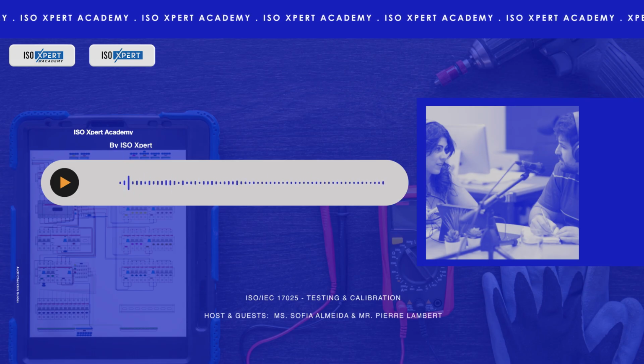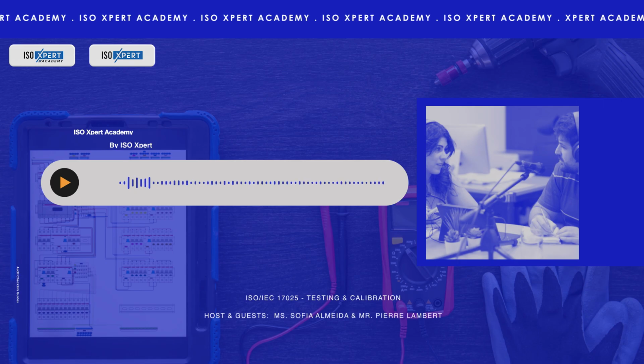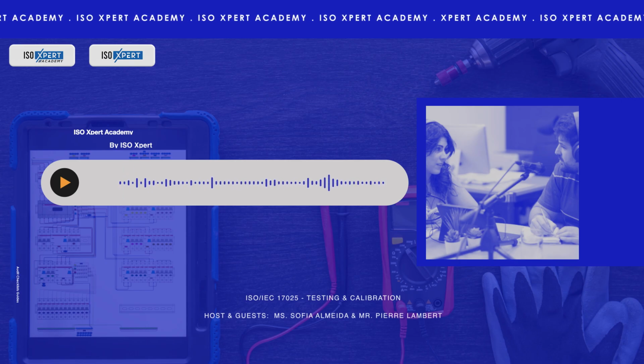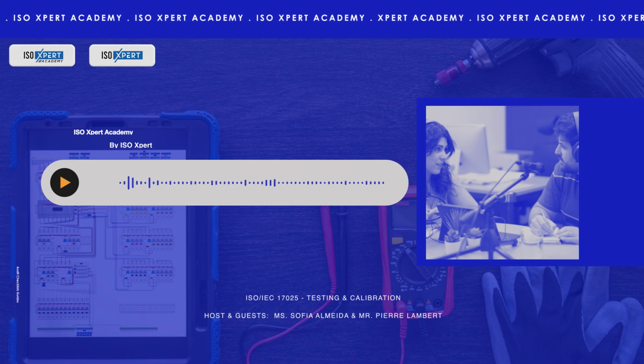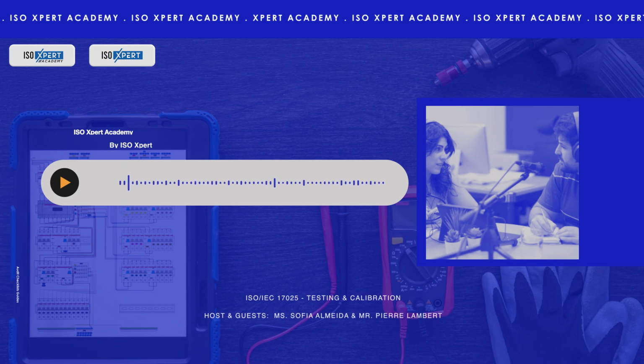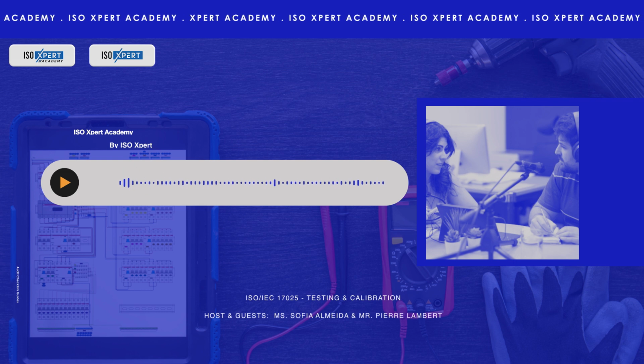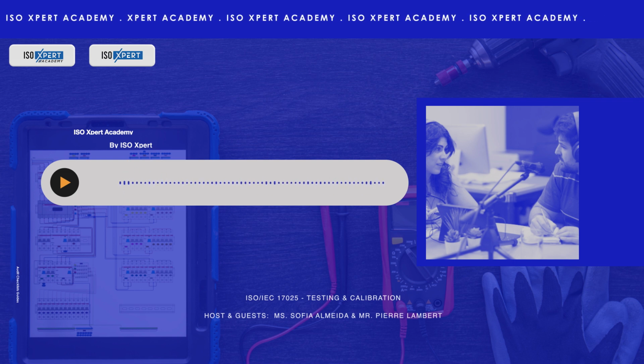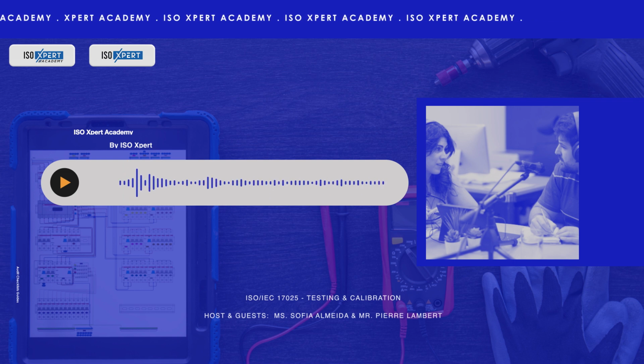Right. A truly competent lab understands this. They quantify it. They document this inherent measurement uncertainty. So they calculate it. Yes. They provide things like MU estimation sheets, uncertainty budgets. These basically map out all the potential sources of error, the instrument calibration, the environment, the sample itself, the operator, and their combined impact on the final result.